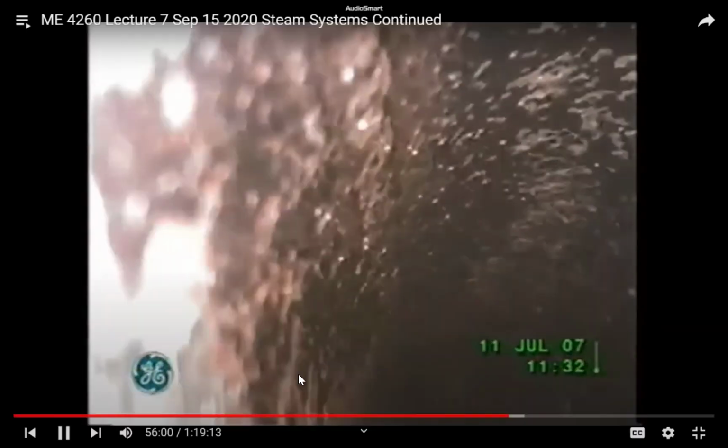If you've got big utility boilers, they'll have a forced draft fan blowing in and an induced draft fan sucking out. And so then the furnace will be what they call kind of balanced pressure. And the pressure is controlled by the capacity of this fan and this fan. If this fan blows more, that'll pressurize it. If this fan pulls more, it'll be negative pressure relative to the environment. But some boilers, smaller boilers, just have a forced draft fan.